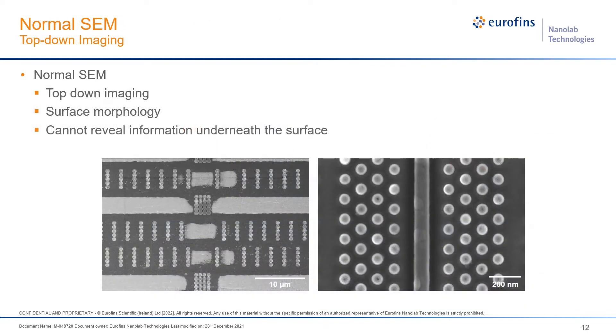A normal SEM can provide high-resolution top-down images of a conductive surface, revealing vias and trenches, and is useful for surface characterization or thin film samples. However, in real manufacturing there are metal layers and dielectric polymers underneath the surface that cannot be observed by normal SEM. So a cross-section is needed for detailed layer information and critical dimension measurements.